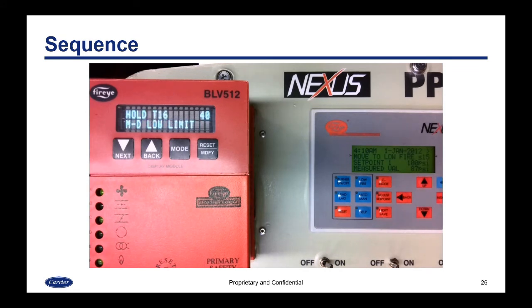So T16, the first thing it's going to do is drive the PPC to low fire. The PPC is going to hold there, and it's actually going to turn the main back off when it gets there and return to PTFI. The PPC is going to stay at the low fire position. Burner Logix is going to stay in PTFI or pilot, and then as soon as we release the revert to pilot, it's going to relight the main and then go back to auto. Meanwhile, the PPC will just have been at the low fire position the entire time.